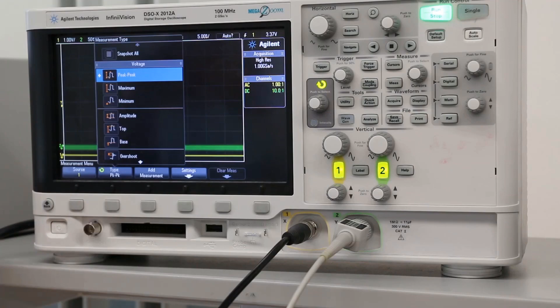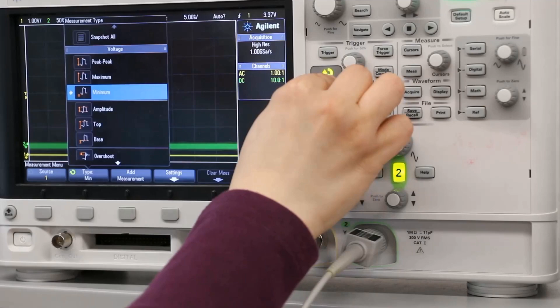select the source. Now it's source 1. Select the type. It's on peak to peak, maximum, minimum, amplitude. So we need the peak to peak, and we can then add measurement. So now peak to peak for channel 1, and then we need the frequency for channel 1. As I said, whenever you see this sign, you use this knob to change the value. So again, we need the frequency, then add measurement. So now we have the frequency and peak to peak for channel 1.